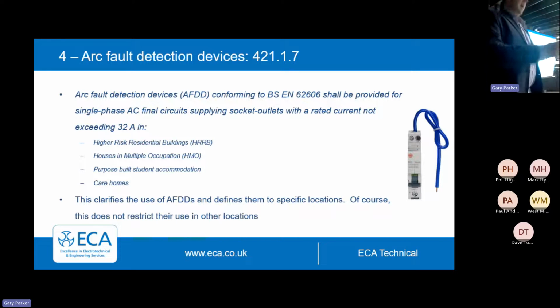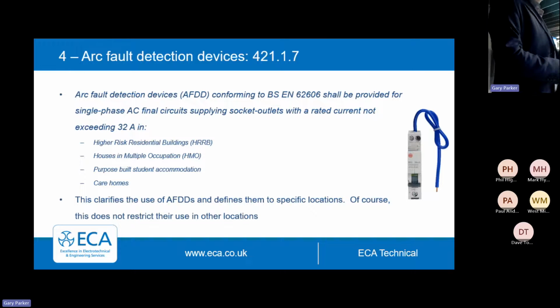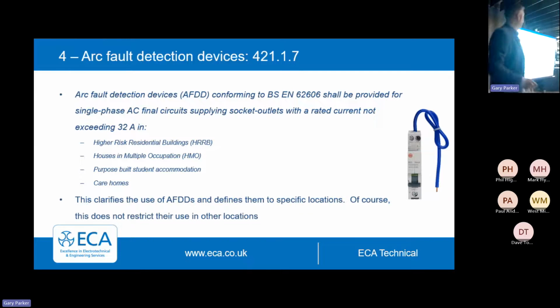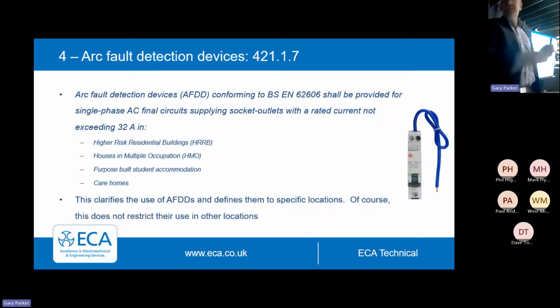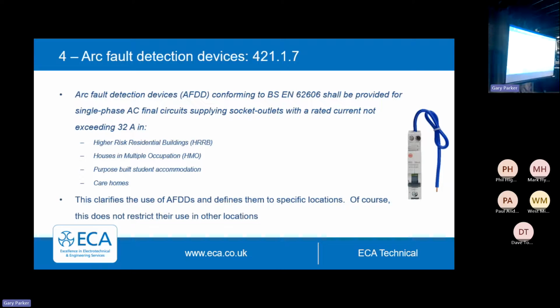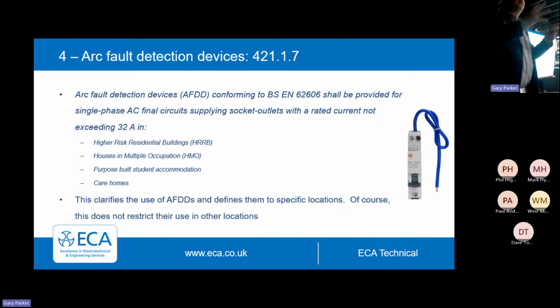Unfortunately, the only two options are you either write it up as a departure from the standard, because the standard says thou shalt fit them. But they're limited in their function and limited in their benefit. They'll protect, if you're doing a student residence, whatever the student has plugged in, but they won't protect that cable in the wall. So it's not like it's a silver bullet protecting everything on that install.